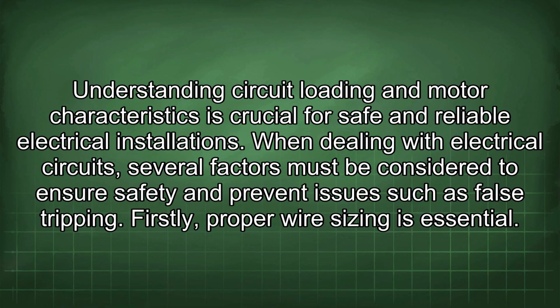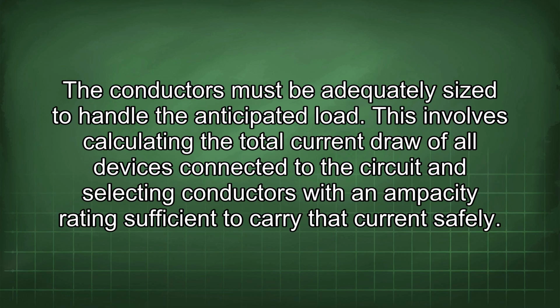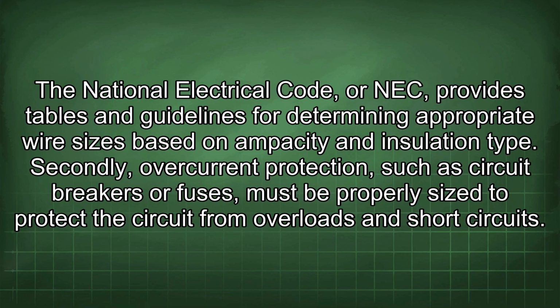Firstly, proper wire sizing is essential. The conductors must be adequately sized to handle the anticipated load. This involves calculating the total current draw of all devices connected to the circuit and selecting conductors with an ampacity rating sufficient to carry that current safely. The National Electrical Code, or NEC, provides tables and guidelines for determining appropriate wire sizes based on ampacity and insulation type.